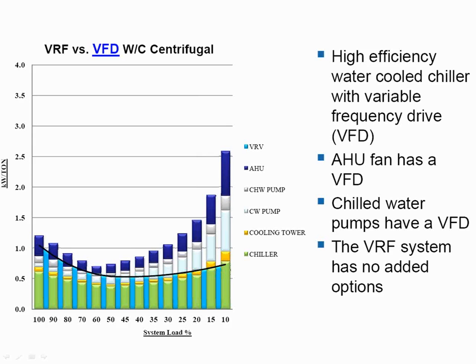However, that's not really a fair way to look at it, and this is coming from a company that we do chillers and VRF. The VRF is what I call an all-in rating. It includes all the distribution costs, including the fan energy of the indoor coil, right? The chiller is just the chiller. If I add the cooling tower to the chiller, then I add the yellow band on there. And the cooling tower does really good until I get to really low loads, and the cooling tower can't really ramp down that much more.